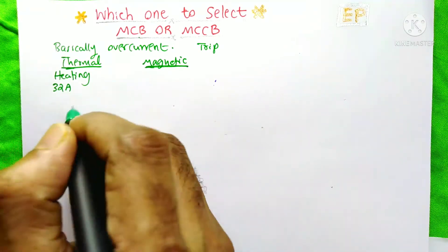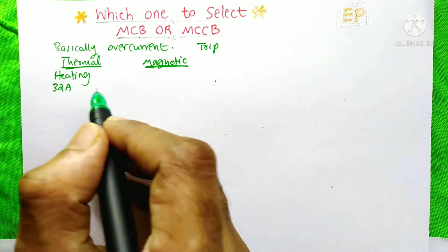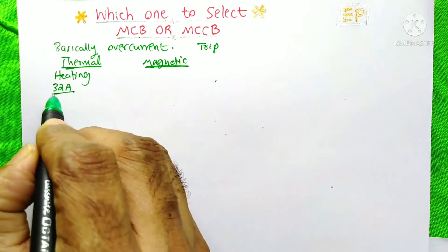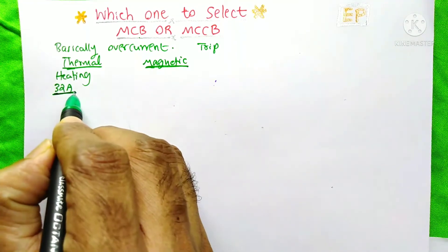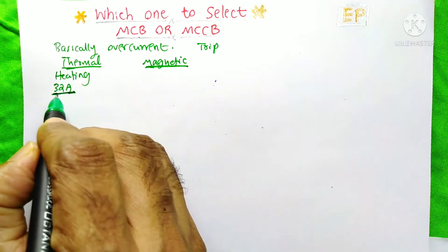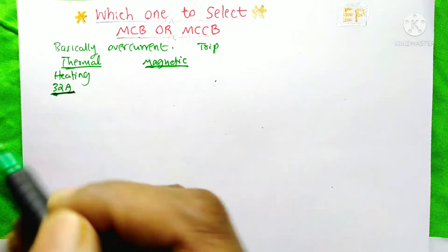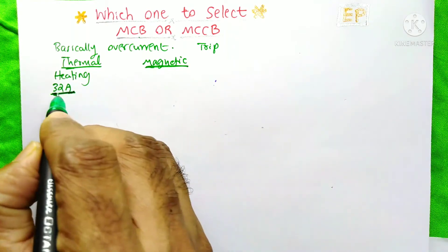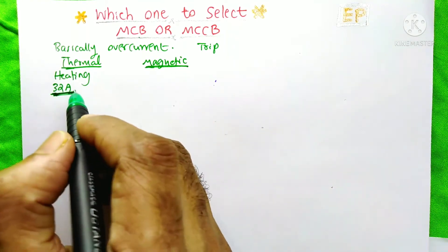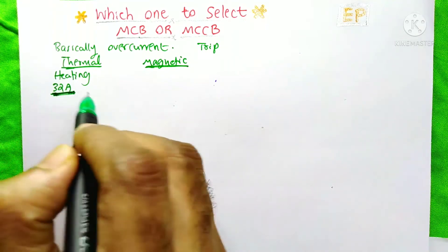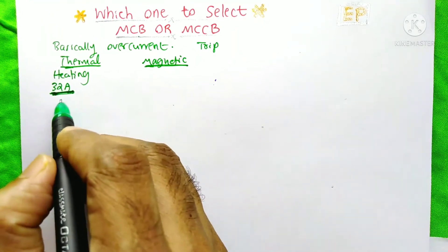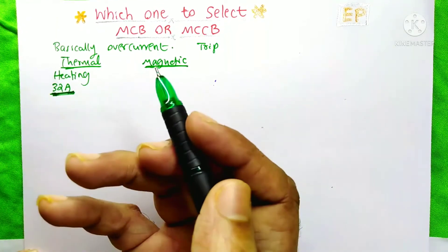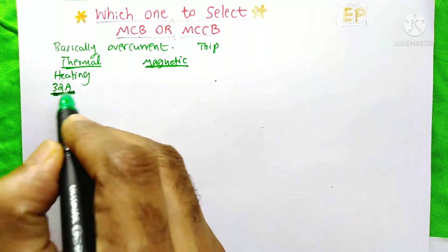After a specific time, the bimetallic strip will bend and the circuit will open, protecting the circuit. Even when the circuit current equals the rated 32 amperes, after a long period — maybe 30 to 45 minutes — the bimetallic strip will bend and break the circuit. Whenever the current is more, the tripping time will be less; whenever the current is less, the tripping time will be more.